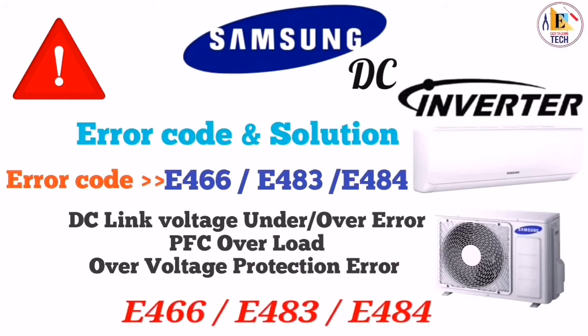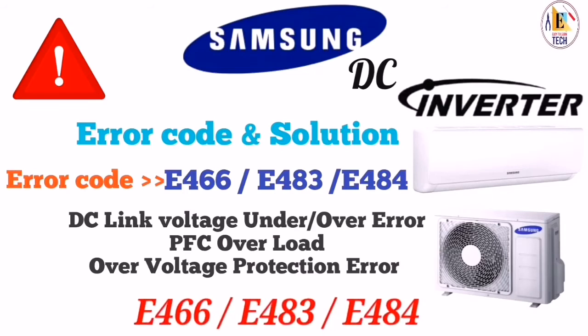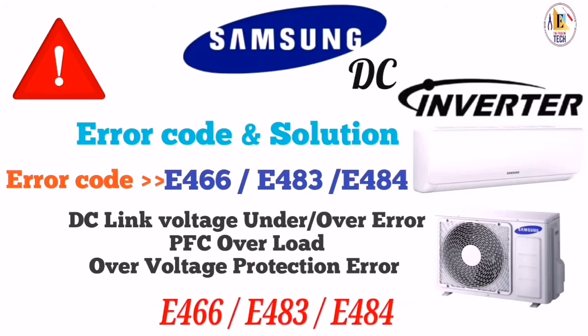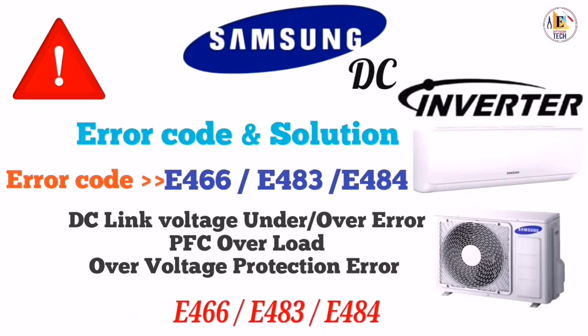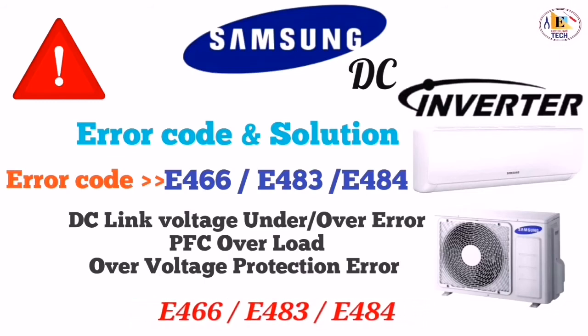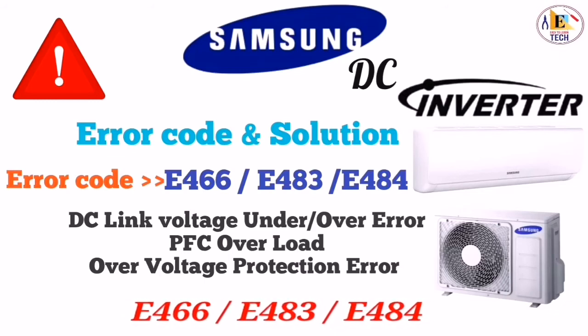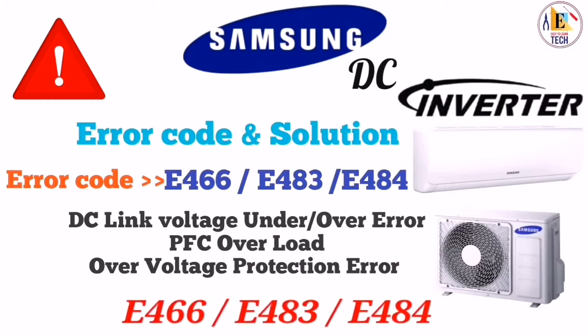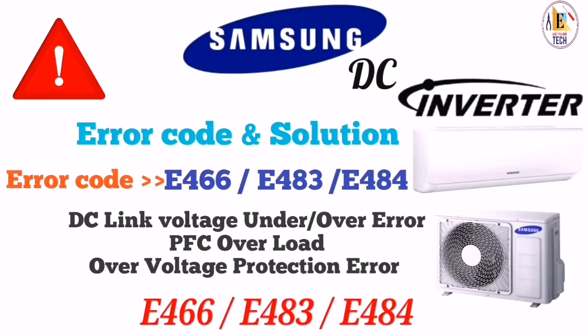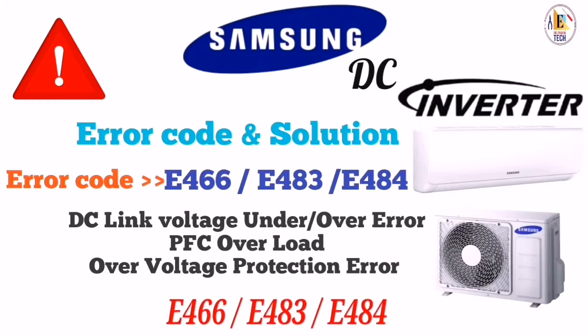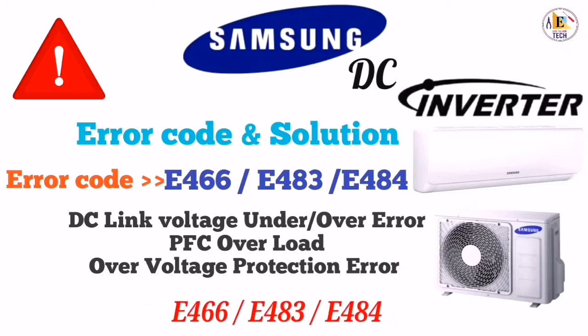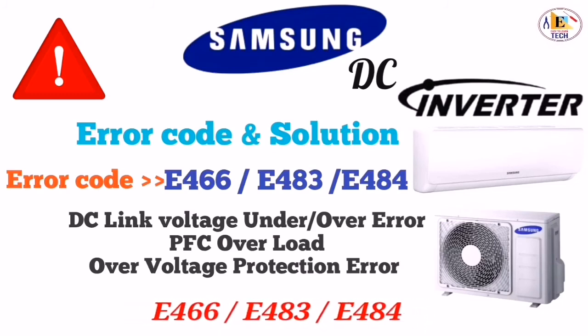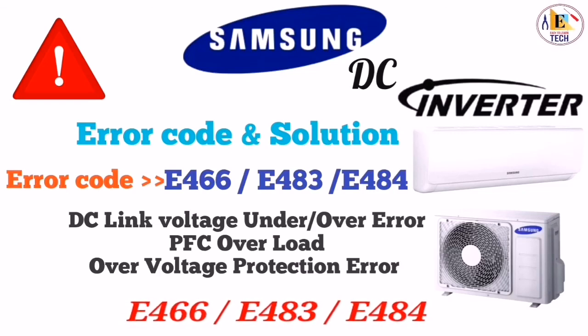In the next process, you have to check whether the DC link sensing voltage D is normal in operation mode or not. The normal range should be 0.2 volt DC to 4.0 volt DC. If you are not getting this voltage, then you exchange your PCB. And if you are getting this voltage, then you have to change the reactor, because the reactor insulation is damaged. Exchange the reactor and your unit will be in working condition.